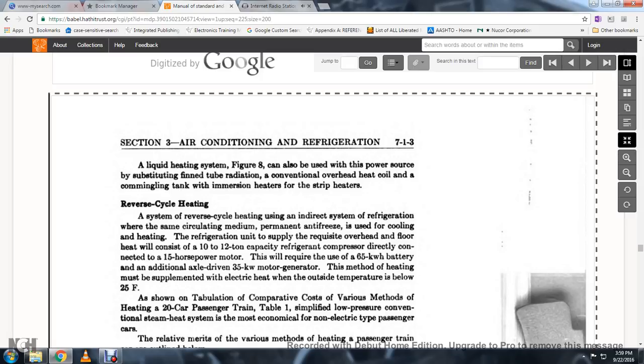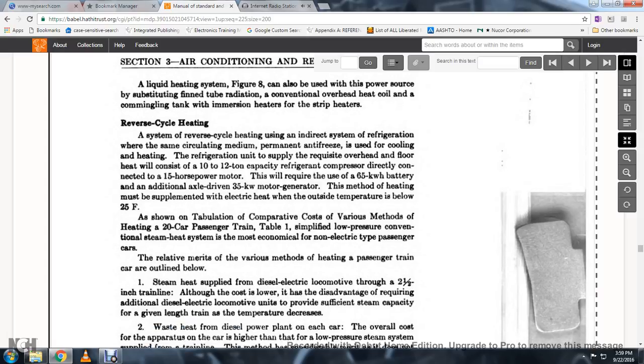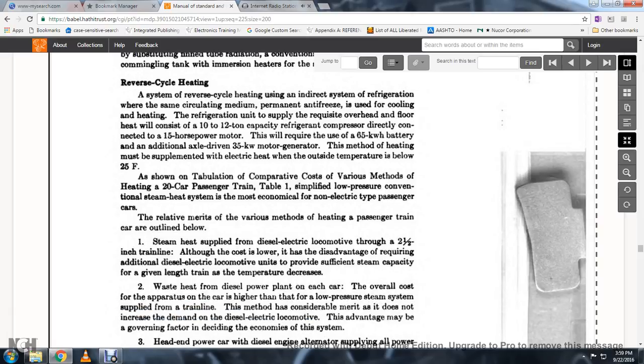As shown in the tabulation comparing the costs of various methods of heating a 20-car passenger train, the low-pressure conventional steam-heat system is the most economical non-electrical type for passenger cars. The relative merits of the various methods of heating passenger train cars are outlined below. Steam heat supplied via diesel-electric locomotive through a 2.5-inch train line has a lower cost, but has the disadvantage of requiring additional diesel-electric load capacity to provide sufficient steam for a given train length and temperature.